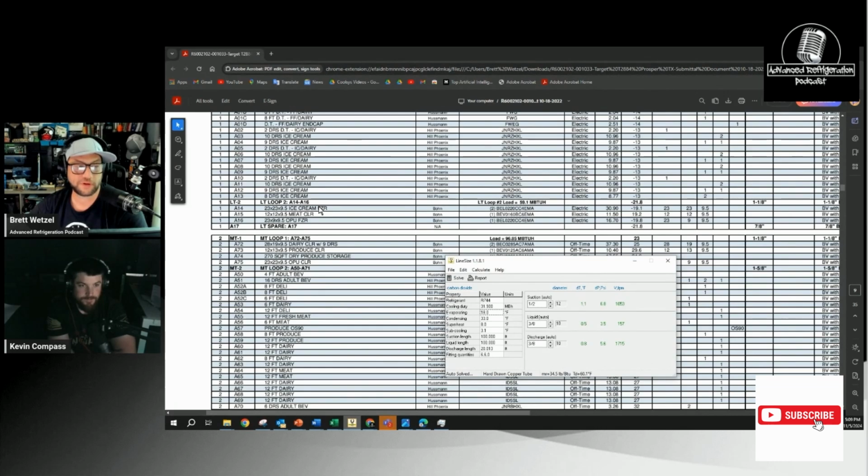I totally agree. Now, do you want to talk about your experience of what you did recently with changing some of the stuff around on that? So we found that on big coils, me and you were both messing around with this, a longer pulse rate is better. Going from 6 seconds, we've tried 8 and 10. Didn't go above 10, but 8 or 10 seem to be like a sweet spot for bigger coils.